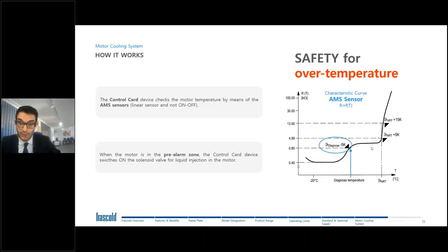And what we do here, we inject fresh refrigerant in the motor. If, however, we go over 110 degrees, there is an alarm, and it's correct in this way to prevent the motor burning. If the temperature goes below 70 degrees, and so the ohmic value is 0.4 kilo, there is absolutely no need for injection, and so we stop the injection. So we call this zone the pre-alarm zone. It's the zone where the control card device switches on the solenoid valve and injects the liquid in the motor. So a very safe system for the motor itself and so for the compressor itself.